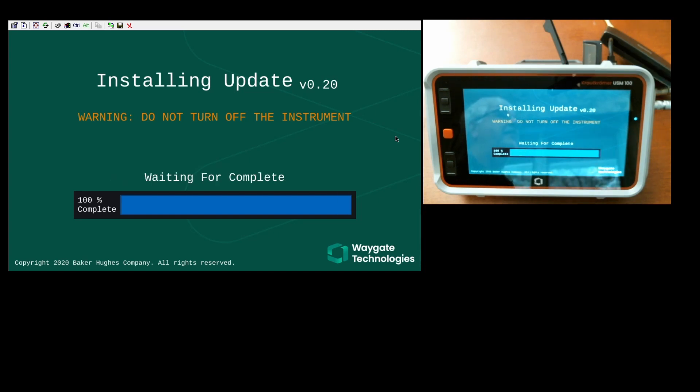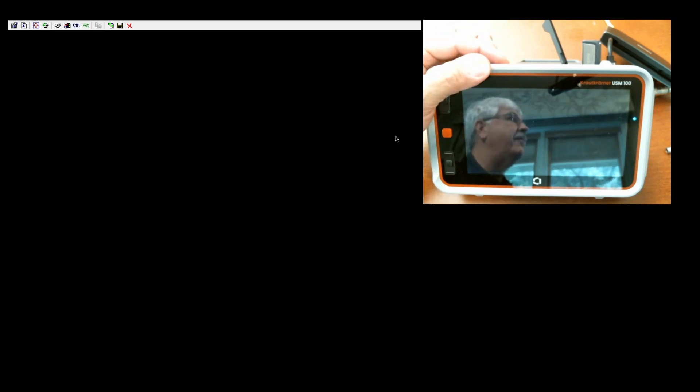OK, at the very end of the process, the instrument will appear to turn off. We'll see the update window go away as we lose our connection as the computer begins shutting down. Now, unfortunately, there's a small bug at this point in the process right now. The instrument has not turned all the way off. If you notice, the LED is still lit over here. Even if I unplug the charger at this point, the LED is still lit. So what I'm going to do is do a forced power down. I'm going to reach up to the top here. I'm going to press the power button. I'm going to hold that for 10 to 15 seconds. At some point in that 10 or 15 seconds, we see the LED turn off. We'll hear the click. And at that point, we can go ahead and reboot the instrument with the normal power on sequence.